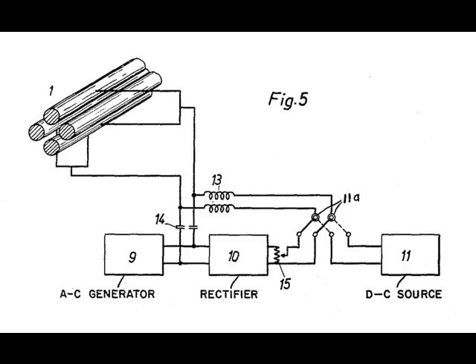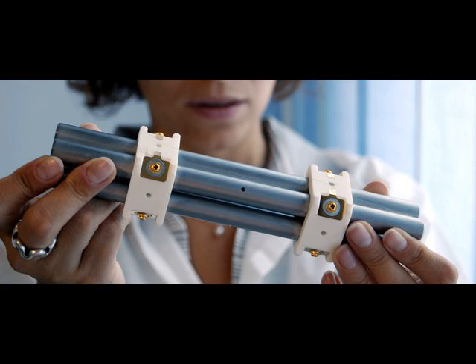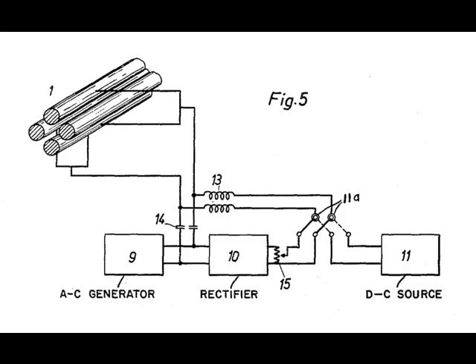Ideally, the rods are hyperbolic. Circular rods with a specific ratio of rod diameter to spacing provide an easier-to-manufacture adequate approximation to hyperbolas. Small variations in the ratio have large effects on resolution and peak shape. Different manufacturers choose slightly different ratios to fine-tune operating characteristics in context of anticipated application requirements. In recent decades, some manufacturers have produced quadrupole mass spectrometers with true hyperbolic rods.